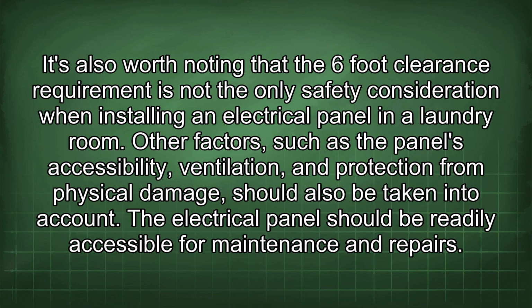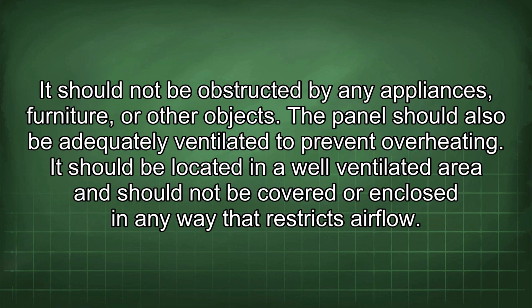It's also worth noting that the 6-foot clearance requirement is not the only safety consideration when installing an electrical panel in a laundry room. Other factors, such as the panel's accessibility, ventilation, and protection from physical damage, should also be taken into account. The electrical panel should be readily accessible for maintenance and repairs. It should not be obstructed by any appliances, furniture, or other objects. The panel should also be adequately ventilated to prevent overheating.